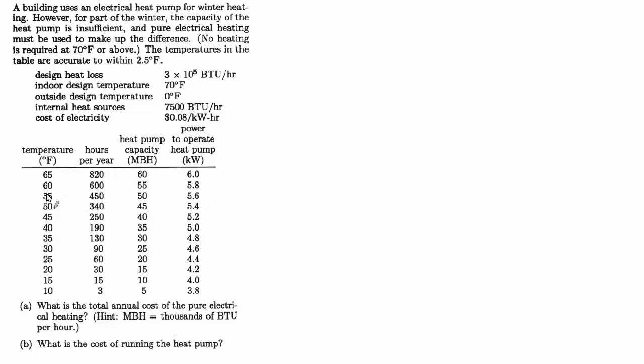So you'll notice as it gets colder and colder, there's less and less hours spent at that temperature. And also you'll notice if you add up all these hours, it does not add up to the total number of hours in a year, 8760, because for a decent percentage of the year, it's 70 degrees or above, and no heating is required. We also know the heat pump capacity, which changes as a function of the temperature outside.